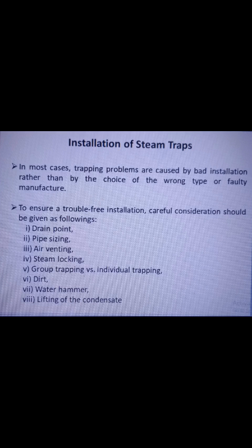The first one is the drain point, then pipe sizing, air venting, steam locking, group trapping versus individual trapping, dirt, water hammer, and lifting of the condensate. Now I will discuss them one by one. First one is the drain point. The drain point should be arranged so that the condensate can easily flow into the trap.